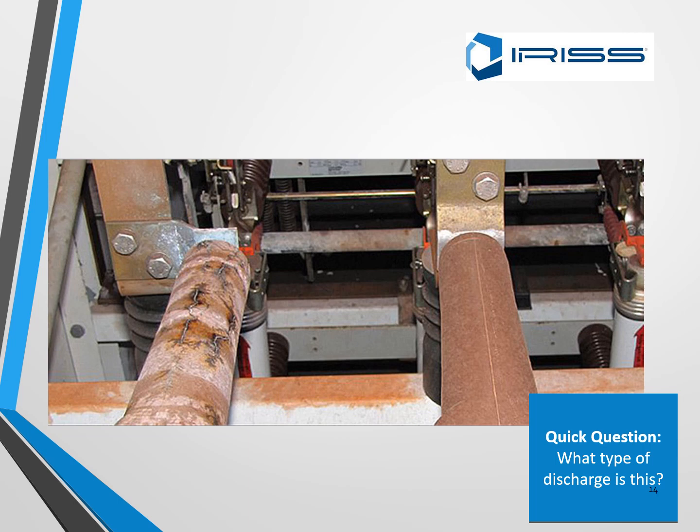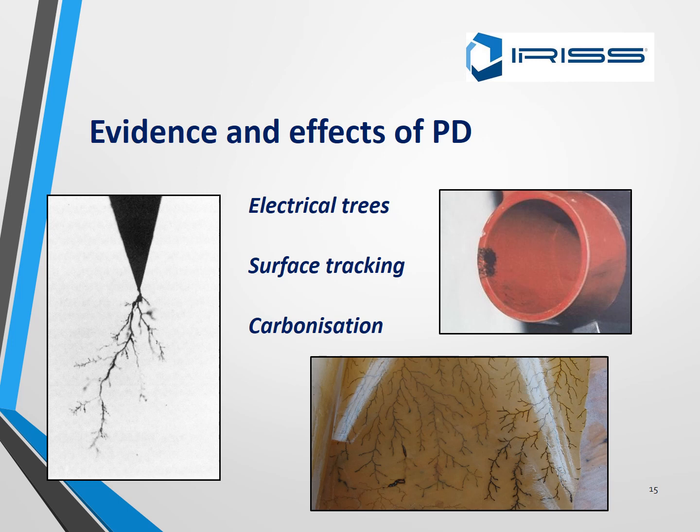A quick question: what type of discharge is this? As you can see, we started with corona — we know it's corona because of the white powder — but it has now progressed to something else: tracking. You can see the carbon residue as well. This slide shows further evidence of the effects of PD — the electrical tree, surface tracking, and carbonisation.